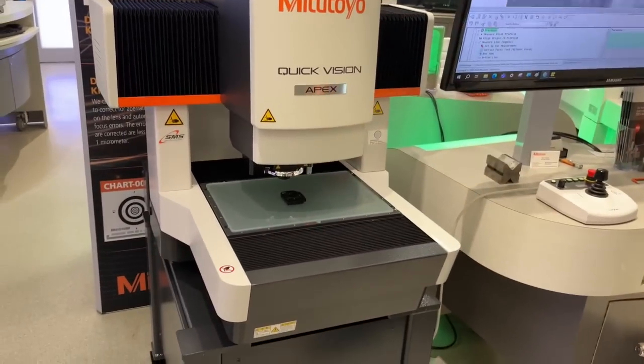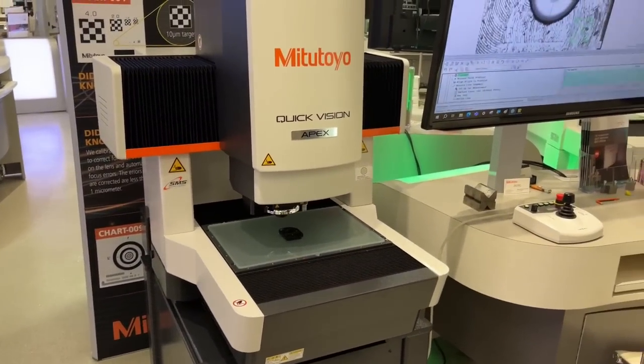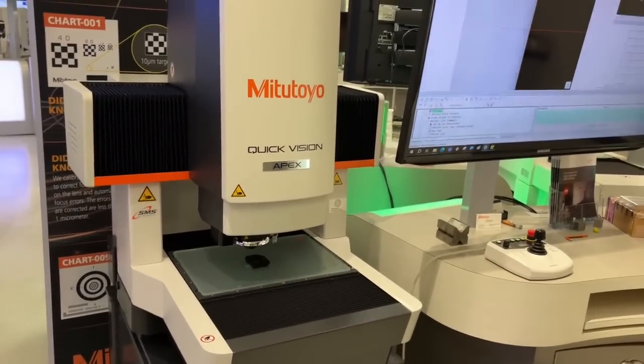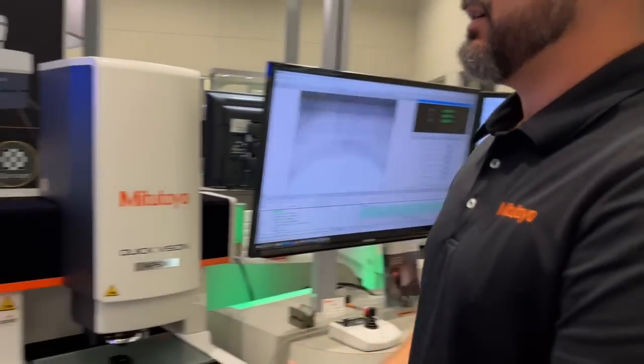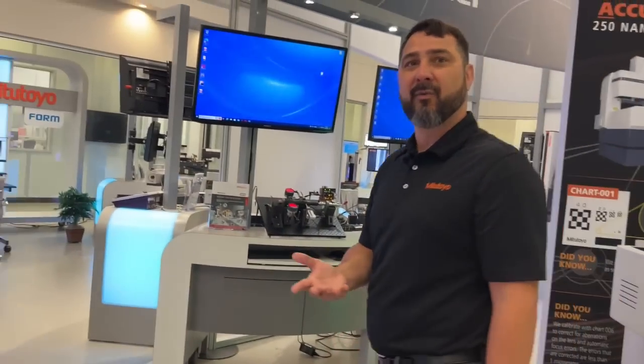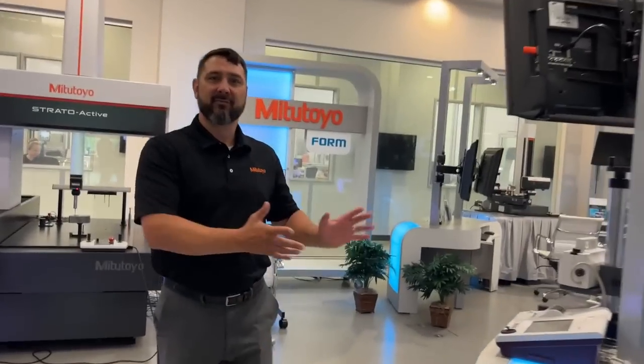You can even get a video system and have a secondary sensor like a touch probe. That way you can measure quick with the camera, and if you can't see something with the camera, you can send the touch probe and go down in a hole or a side hole or what it might be. So very flexible machines. You can have a CMM with touch probe and camera too, so it depends on what platform you really want, but these are very popular systems as well. So you have CMM, VMM, and then the crazy category is the third one called form. And they're all stuffed in a category that does them well one by one.